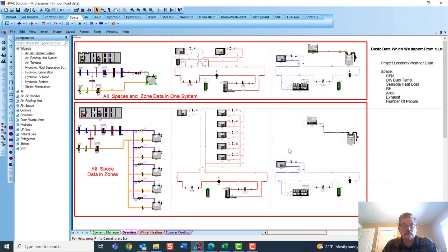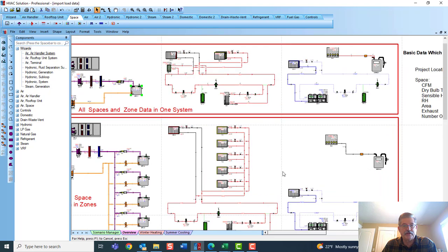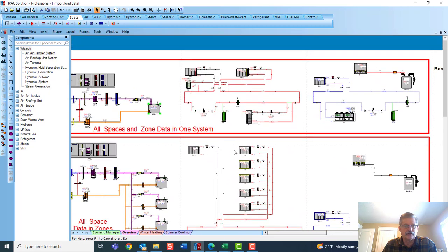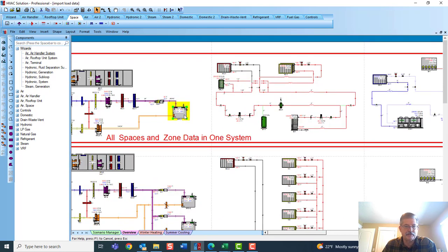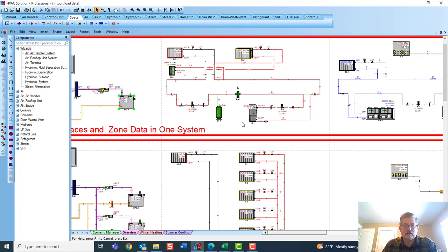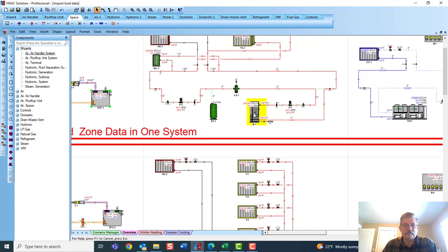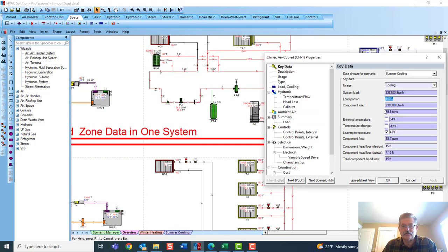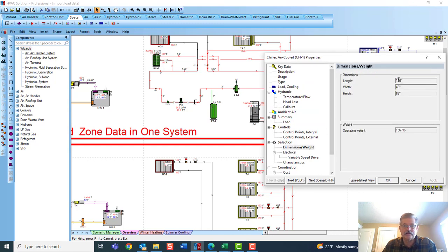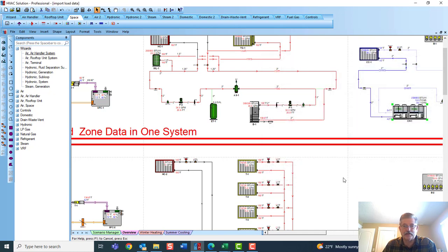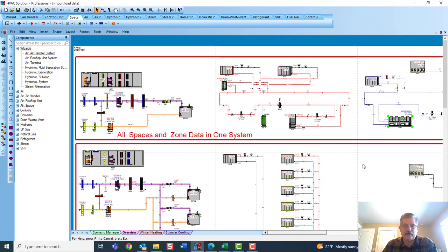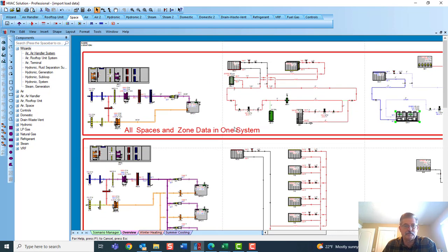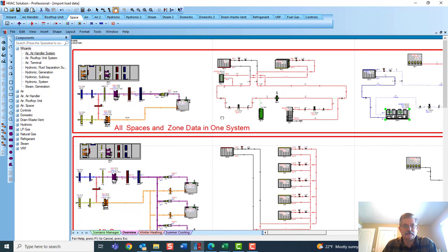So anyway, the reason I like to do this early on in a job, whether I have the loads run or I just kind of estimate the CFM and put that in here, is that now I can automatically know what sizes are of my boiler and air-cooled chiller. You'll see when we do a selection of equipment, we have that data: length, width, and height, and weight, as well as electrical information that's associated with that. So early on in a project, I can tell the architect how much space I need for that air-cooled chiller outside or the boilers that might be inside. And that just helps move the project along.